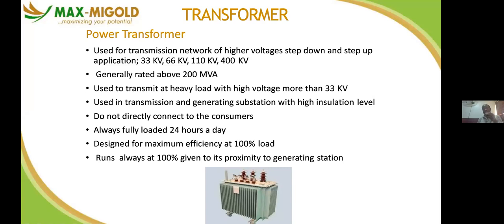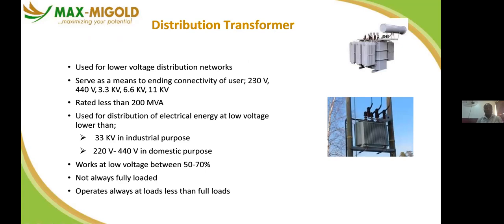Like most offices on the island here, they generate from that generator, which is 415, step it up to 11, from 11 to a common bar where it is further modified to their taste or what they need. So that's power transformer for you. They operate mainly at 100%. We have the distribution transformer used for lower voltage distribution network. Like I said, we have the step up and the step down. Here you see, they serve as a means of connectivity for users at 230 volt, 440 volt, as the case may be. So this one is user friendly. You can make use of this value of voltage when the transformer steps it down.